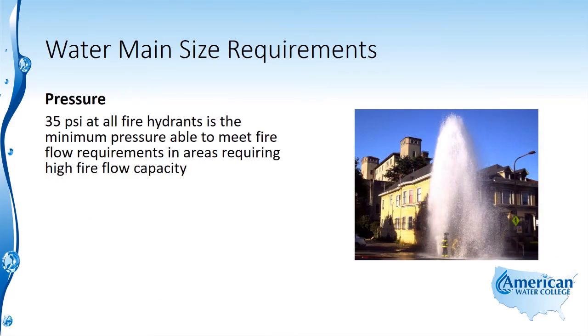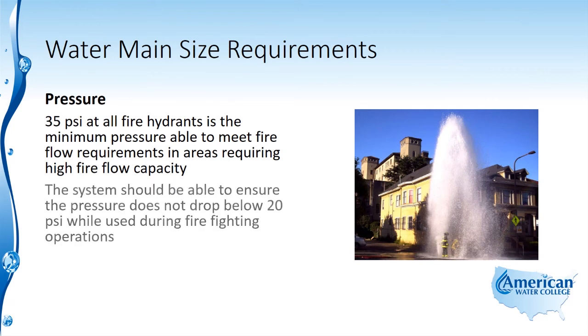35 PSI at all fire hydrants is the minimum pressure able to meet fire flow requirements in areas requiring high fire flow capacity. The system should be able to ensure the pressure does not drop below 20 PSI while in use during firefighting operations.